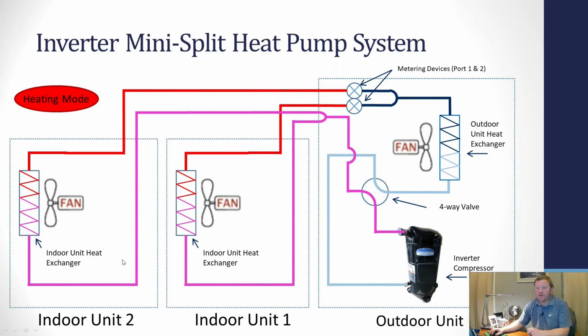So when you have 2 indoor units, now you have 2 algorithms. Now you have one compressor trying to achieve two different target temperatures. Indoor unit 1 that's in my living room might be set for 70, which means it has a target temperature of 73.5. Remember, that's the example we just went through that started with a room temperature of 65. Indoor unit 2 in the master, though, might have a set point of 72. With the offset built in, that's 75.5 degrees for the target temperature. So now the compressor has to decide how hard to run based on both of those units' PID algorithms.